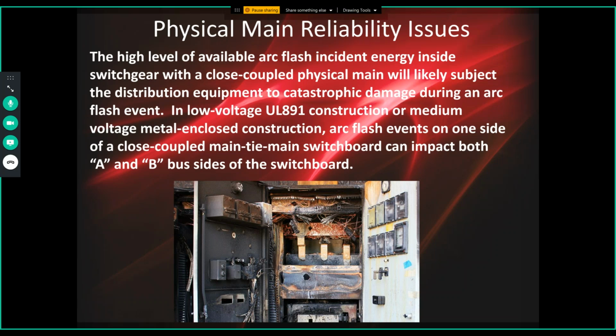So the problem, of course, with a physical main is reliability issues. There's always a tremendous amount of arc flash incident energy. I shouldn't say always, but 99.9% of the time, your transformer is bigger than 125 kVA. You're going to have enough arc flash incident energy to cause injuries up to and leading to death, and permanently debilitating injuries, as well as catastrophically damage the switchboard. This is a switchboard in a main-tie-main application where they thought they were safe, and it propagated to both sides, both the A and B sides of the switchboard, and destroyed everything. This was catastrophic. This was in a wastewater treatment plant, and caused sewers to back up throughout the town. So it's truly a catastrophic event.